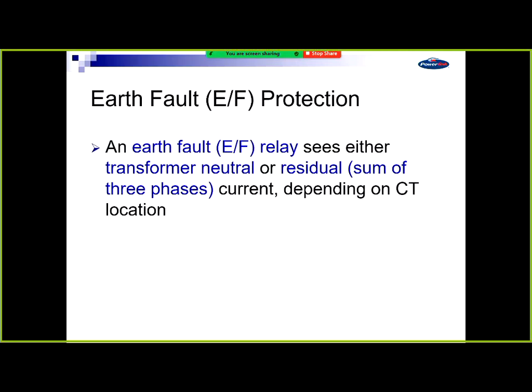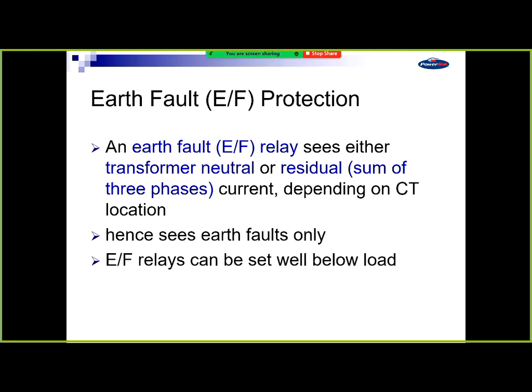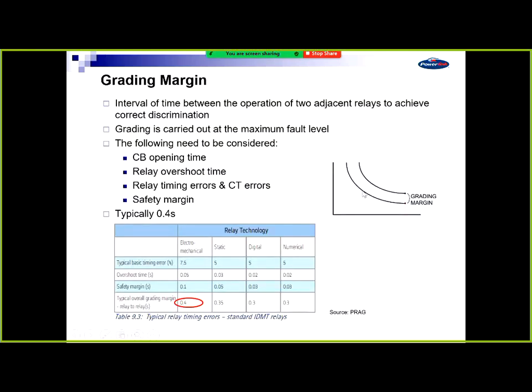Earth faults are either a neutral or a residual sum of the three phases, depending on where your CT is located. They only see earth faults, so you can set them very sensitive. And yeah, they can be set well below load, very sensitive, same sort of comments. The other thing you need to consider, when you do need to grade, is how much margin to use. This again comes from PRAG. You need to allow for CT errors, relay errors, relays operating slower or quicker, breakers operating slower or quicker, and a safety margin.